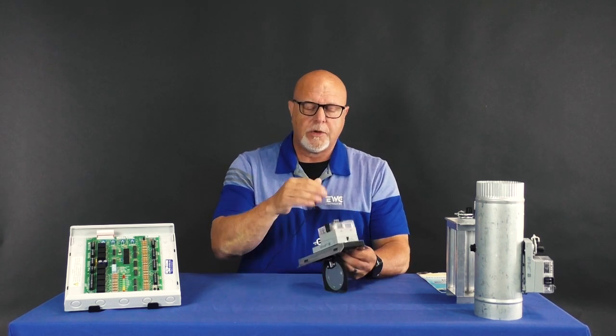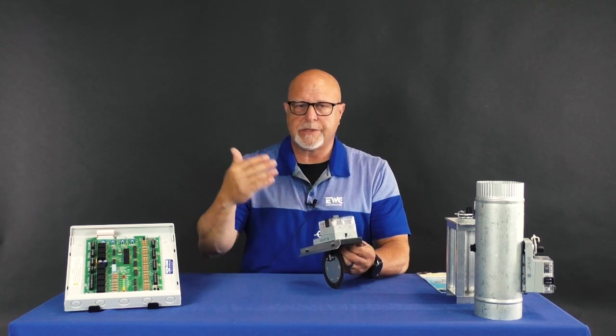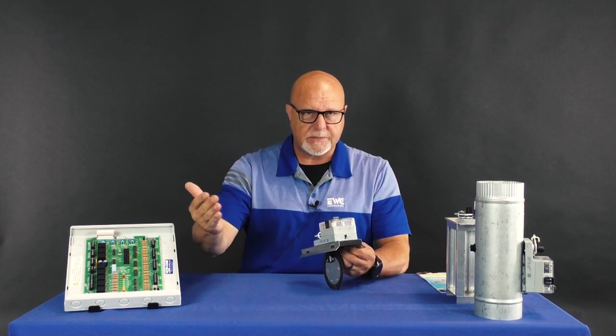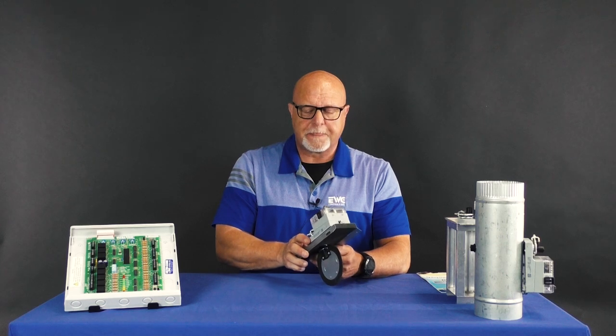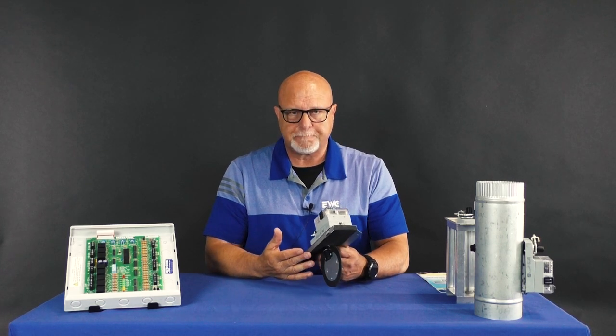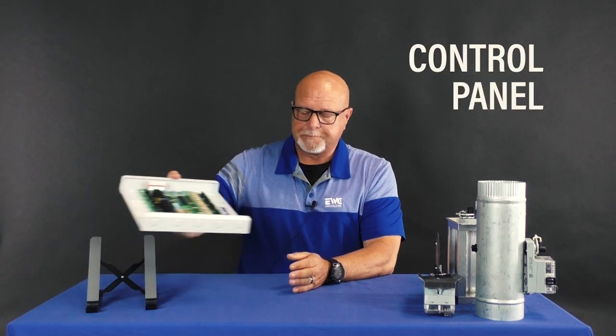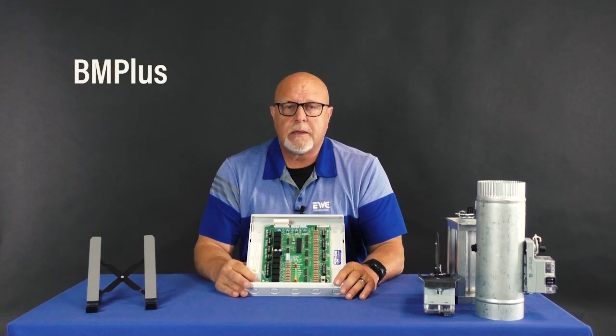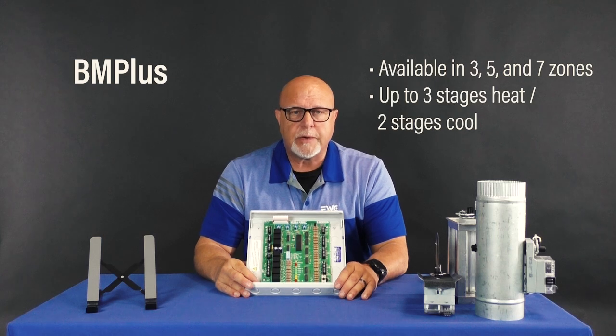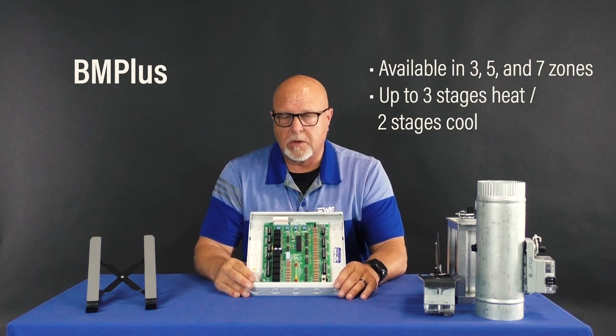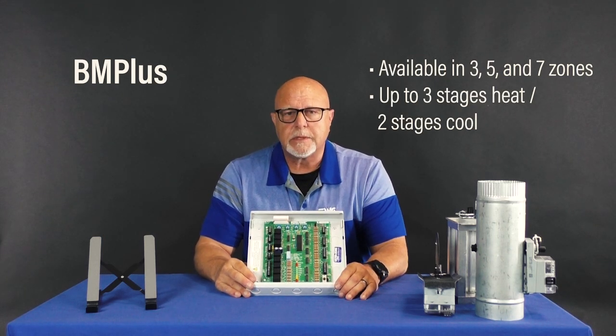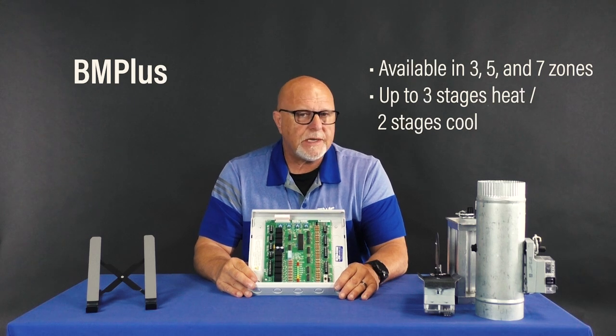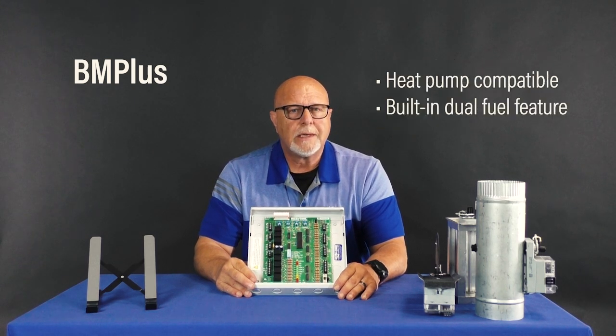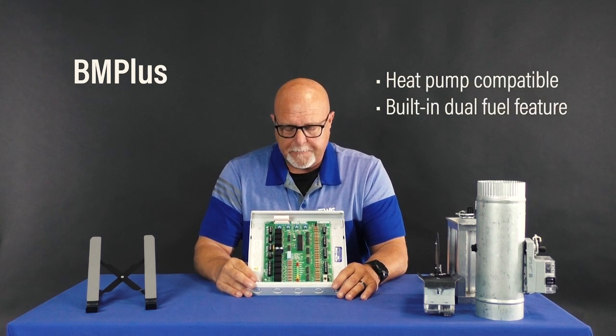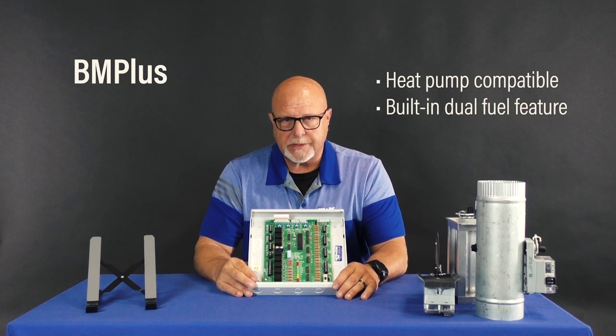Then at that point, you would wire these dampers in series or in a daisy chain type situation, making your individual zones. So moving along with the control panel, this is our BM Plus line. It's available in 3, 5, and 7 zones. It's able to handle up to 3 stages of heat, 2 stages of cooling. It's heat pump compatible, and it has the dual fuel feature built in.